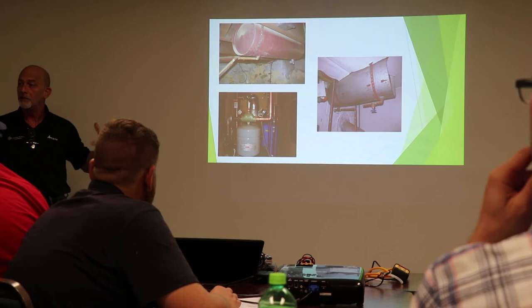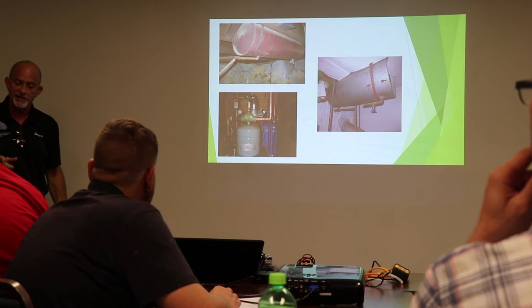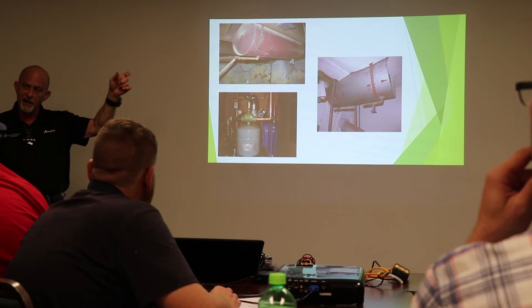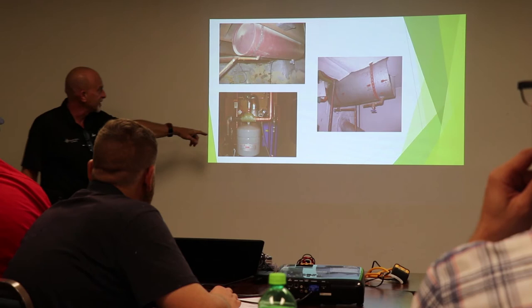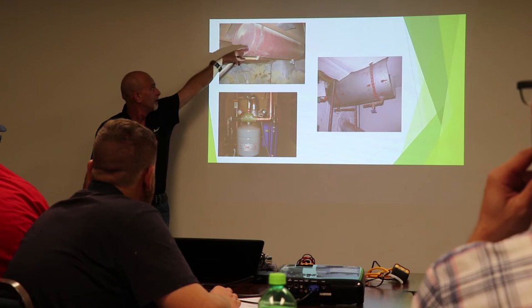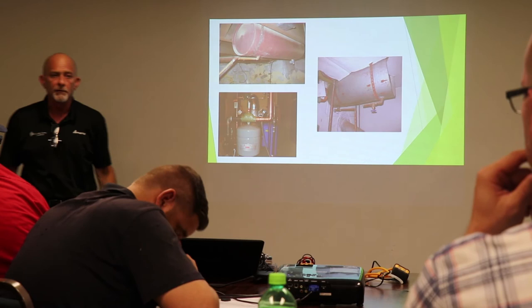You can tell if an expansion tank's working or not by tapping on it. Solid sound, dead sound. Air gap. If it's completely solid here, the tank's bad. Same thing with here. Solid sound, tank's bad. It's full of water.